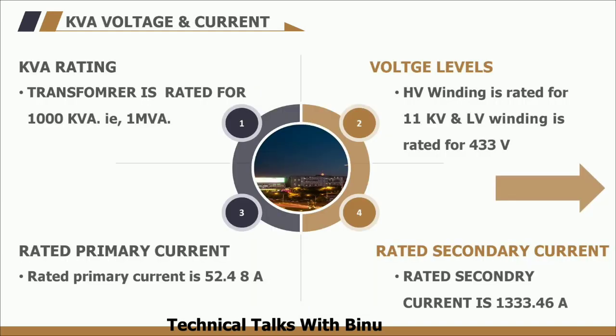The next parameter is the KVA rating of the transformer. We have already discussed how to select the KVA rating of a transformer in our last video — I have given the link in the description box. Coming to our example, the rated capacity is 1000 kVA, which means 1 MVA. The rated voltages are 11 kV on the HT side and 433 V on the LT side. The rated current on the HT side is 52.48 amperes and on the LT side is 1333.46 amperes.